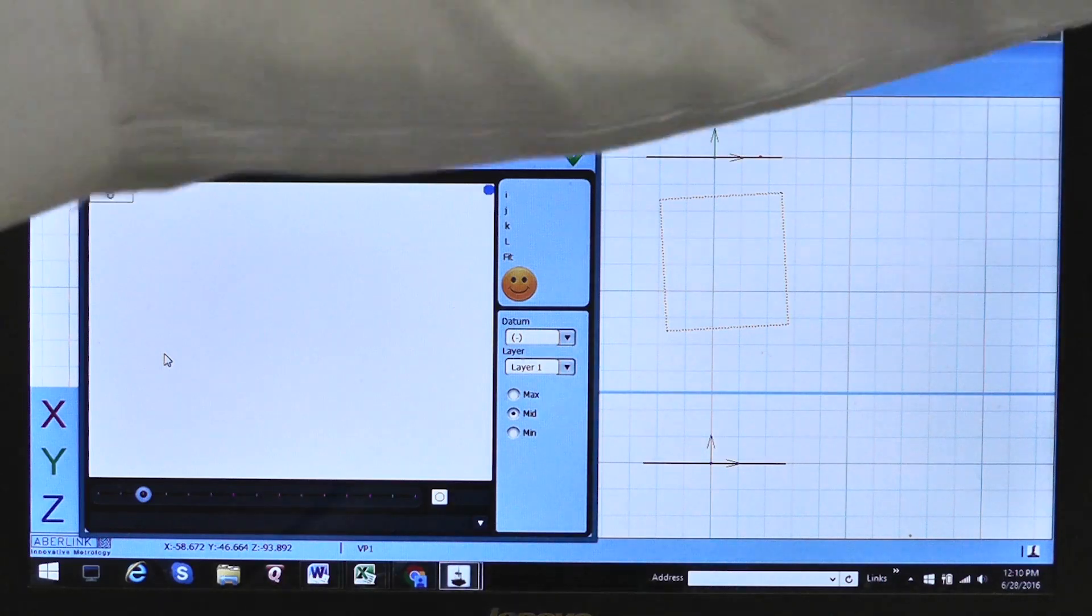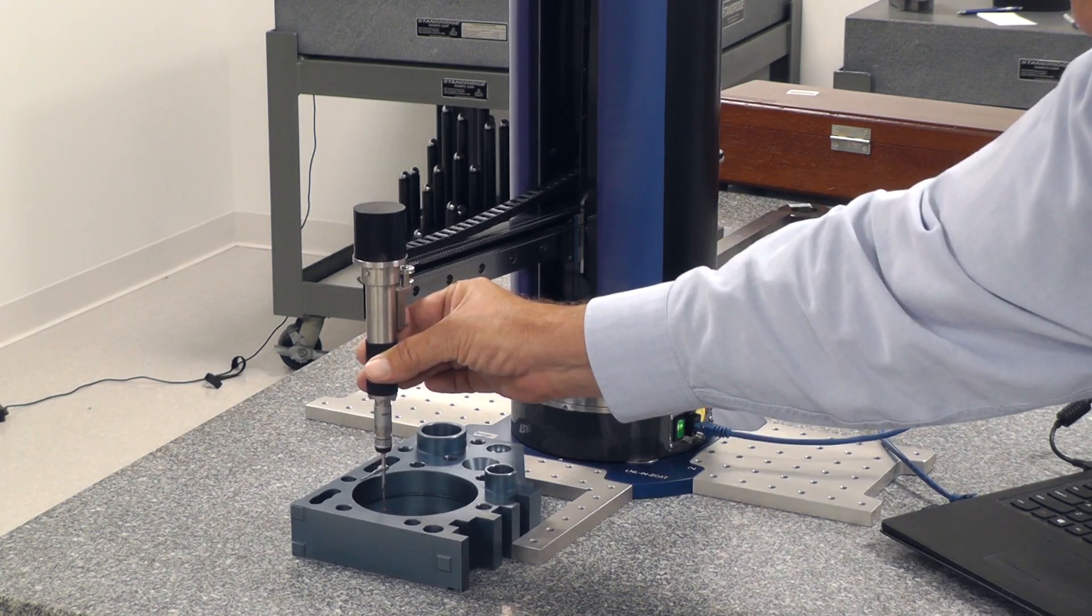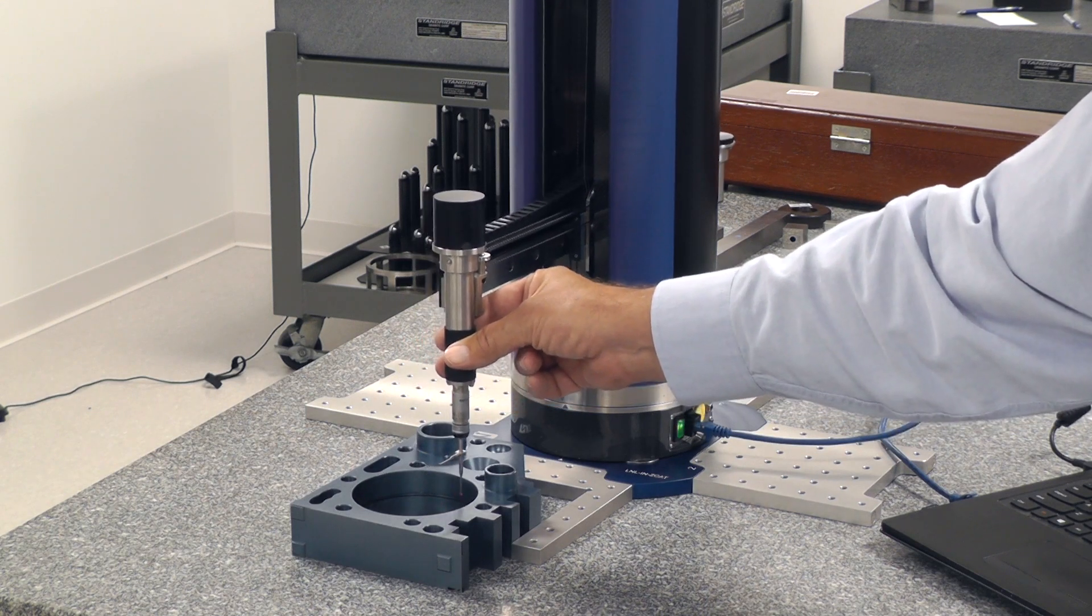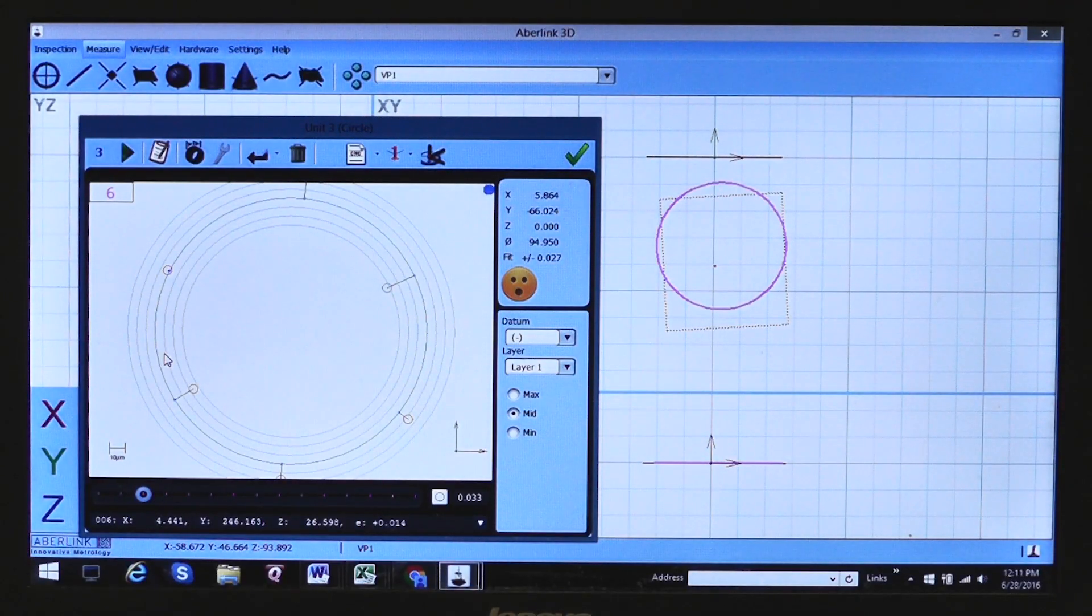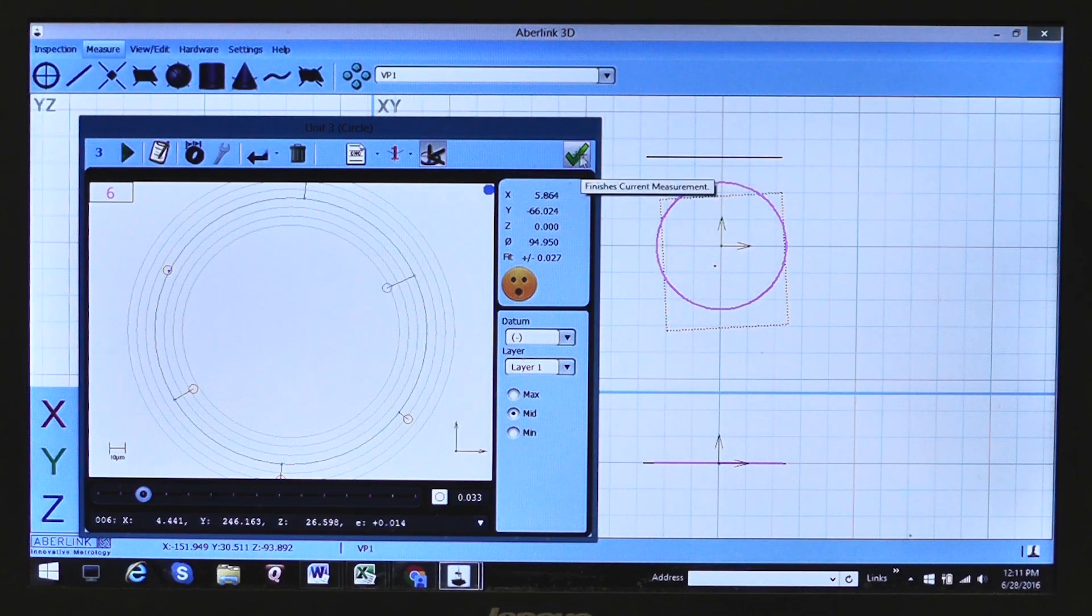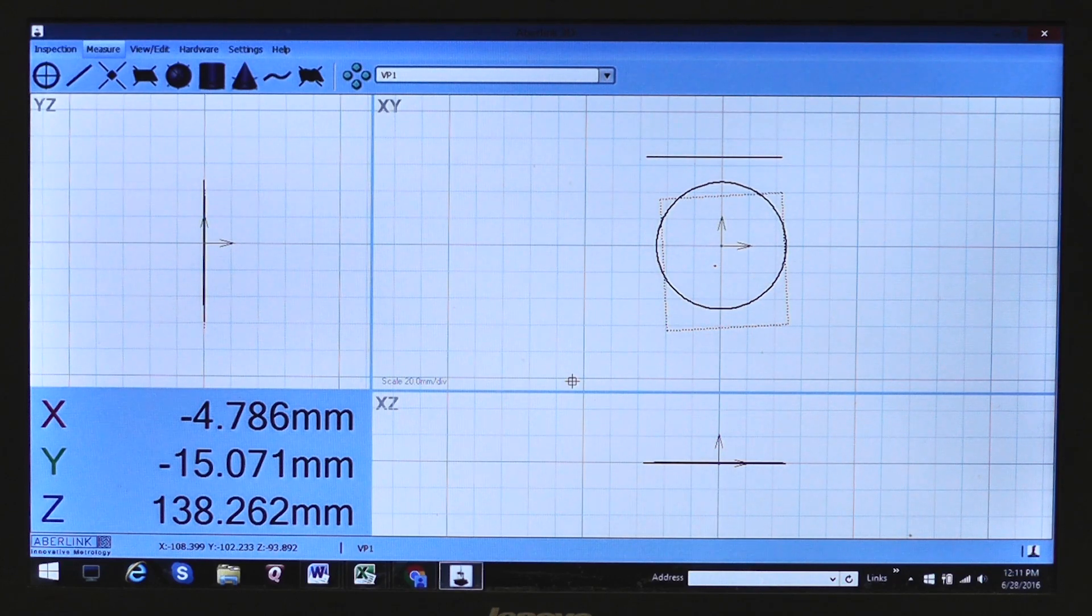Now let's do a circle. If I click on the circle icon, it tells me this is unit number three. It is going to be a circle. I haven't taken any points yet. There's a zero on my upper window. I can now physically come down, touch a minimum of four points to get a good circle, but let's go ahead and take six points on here. And it will give me the circle on here. And I'm going to also make that a reference, so that will actually make the center of that circle the zero point on this part. So all the operator has to do is physically come in, touch on the dimensions that he wants. It will create those dimensions.